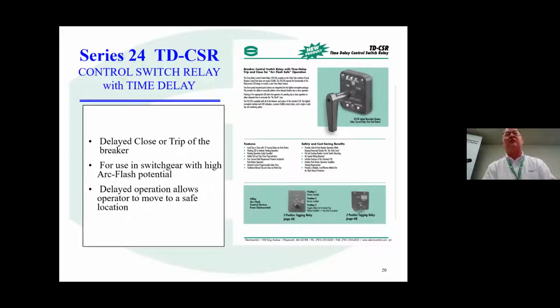We do have a special CSR, control switch relay, called the TD-CSR, which is a combination of a control switch relay and a time delay function for arc flash mitigation applications. Essentially, it allows you to manually walk into a substation and operate a breaker through the TD-CSR by giving yourself time to set the trip function, leave the space, have the breaker trip after a period of time, and then you can come back into the space and do your maintenance on that breaker in that substation without exposing yourself to arc flash issues under the OSHA 70E requirements that you might find yourself involved in some areas. So let me show you what that looks like and how that operates.